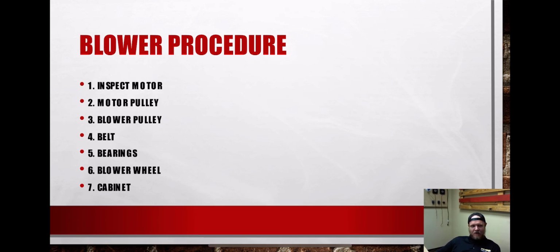Use your senses. Inspect the motor pulley for glazing and grooves and chunks of belt or loose paint or anything like that. Your motor and your blower pulley, the belt shouldn't get stuck inside of there. Check your belt for signs of drying and cracking and tearing. Your bearings, take your belt off of your motor, spin your blower wheel just by itself. Listen for those bearings. If you can hear the bearings, that's a problem. You shouldn't be able to hear anything. Same thing with your motor. Spin your motor pulley and see if you can hear anything coming out of the bearings on your motor. If you can hear anything, it's probably too late for that motor, and we need to write up that motor.